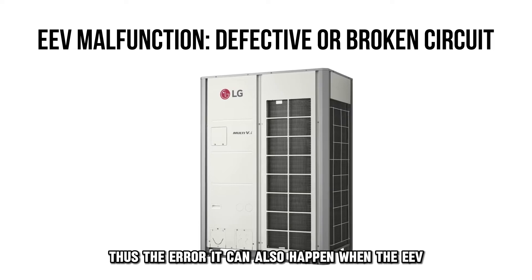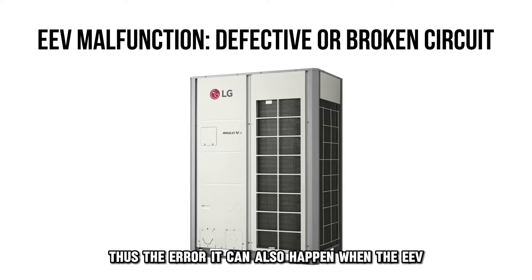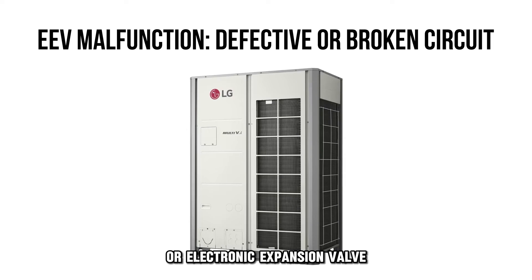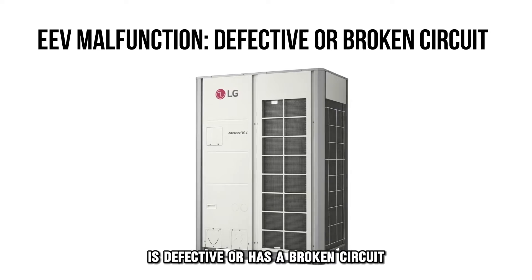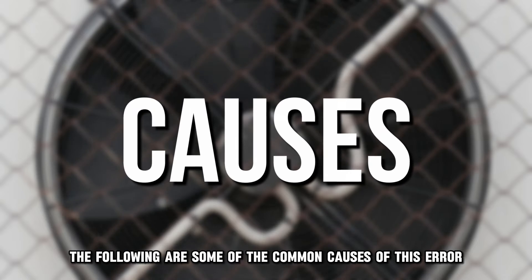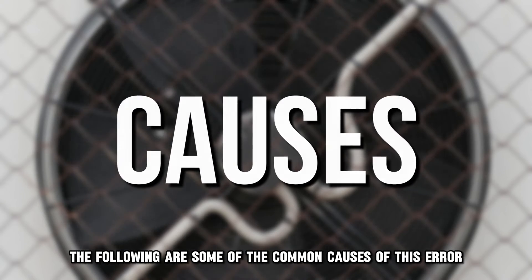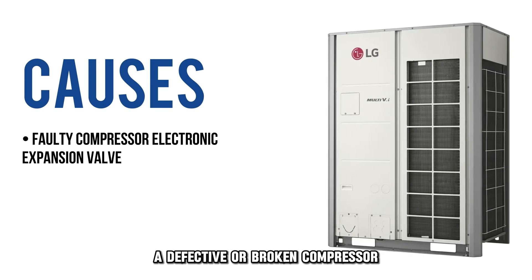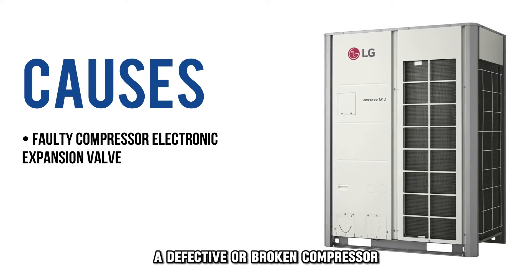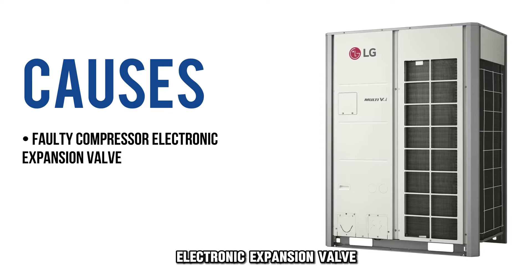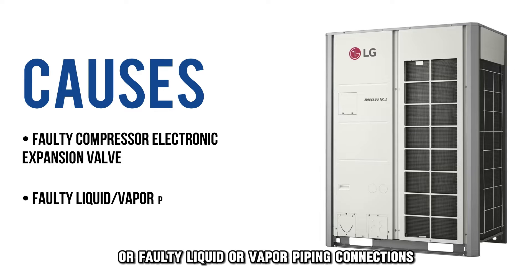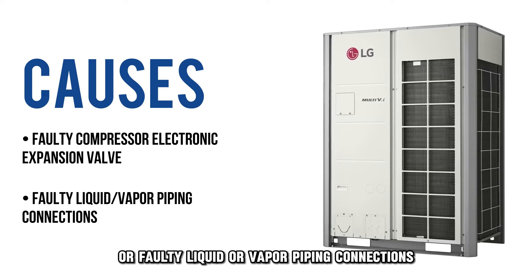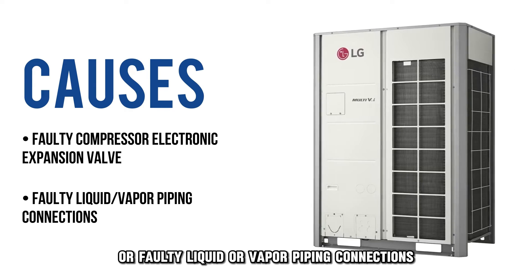It can also happen when the EEV or Electronic Expansion Valve is defective or has a broken circuit. The following are some of the common causes of this error: a defective or broken compressor, Electronic Expansion Valve, or faulty liquid or vapor piping connections.